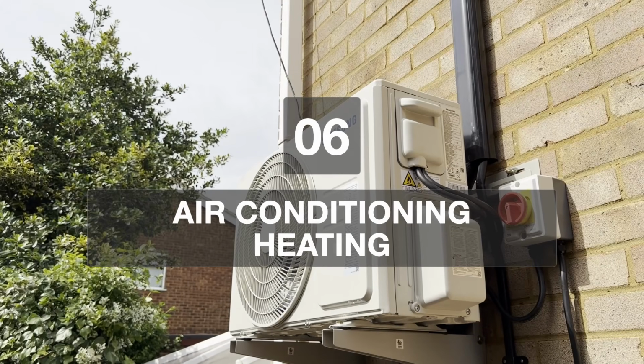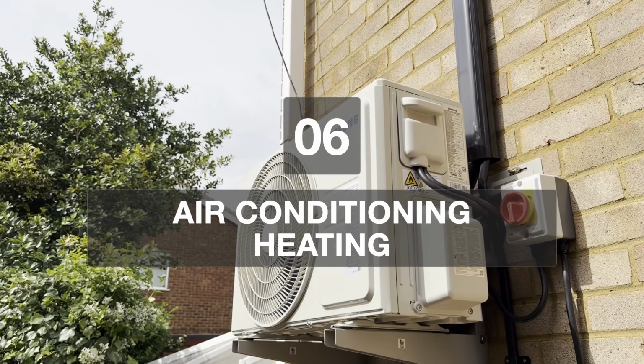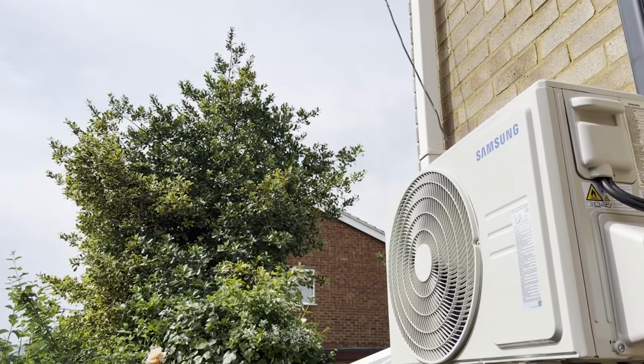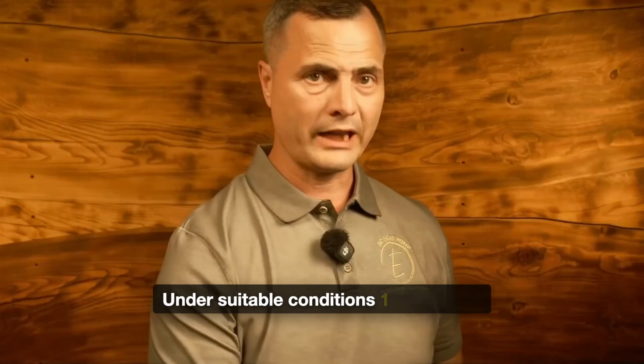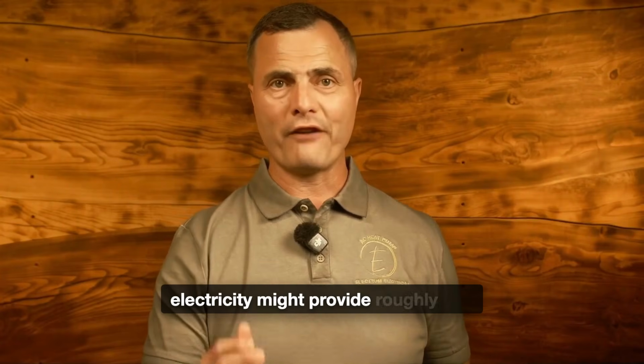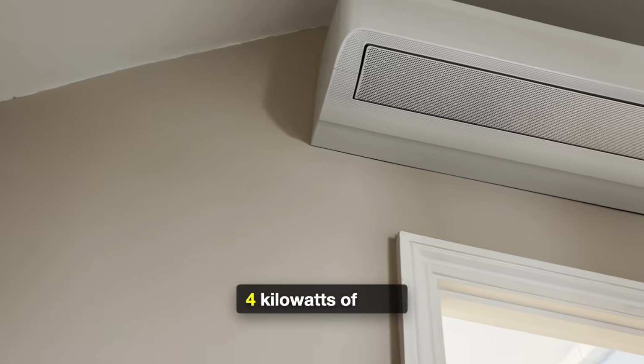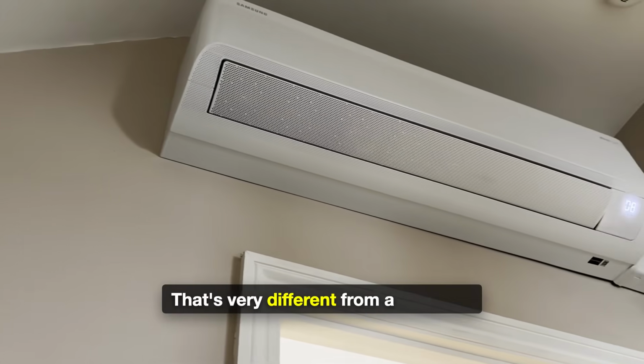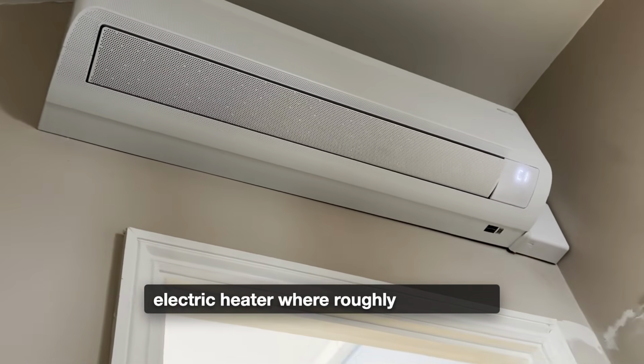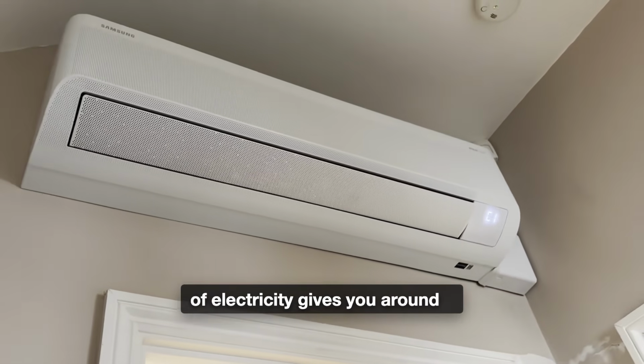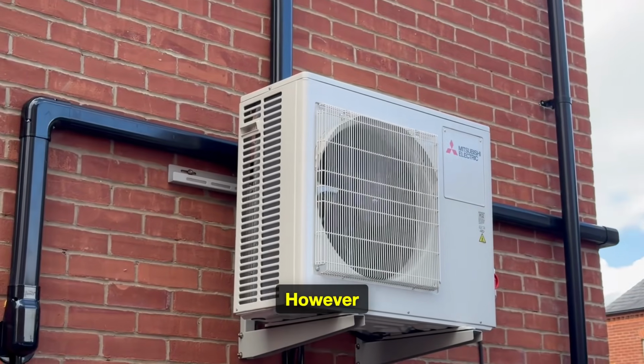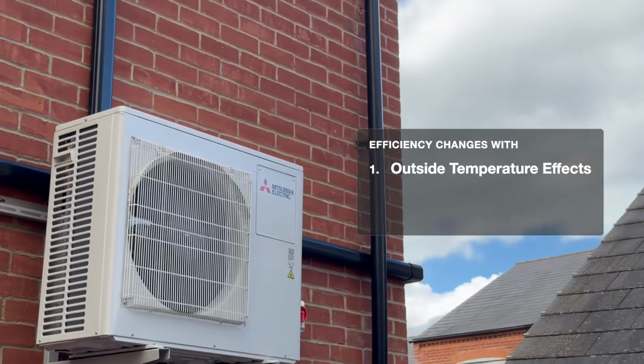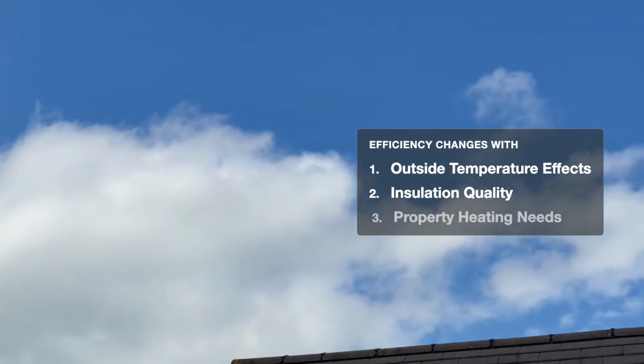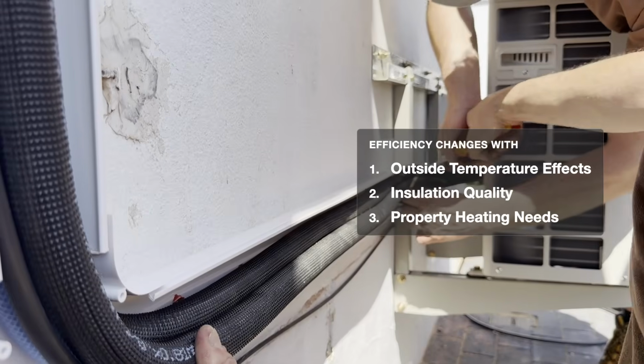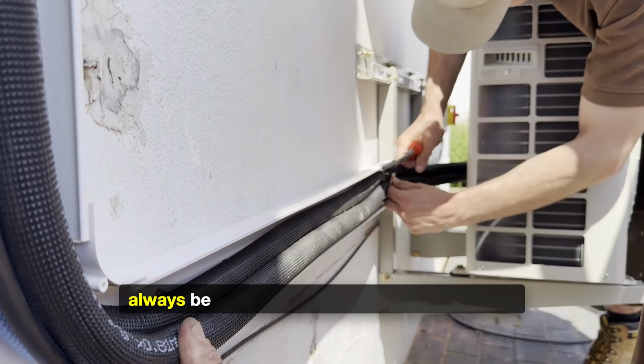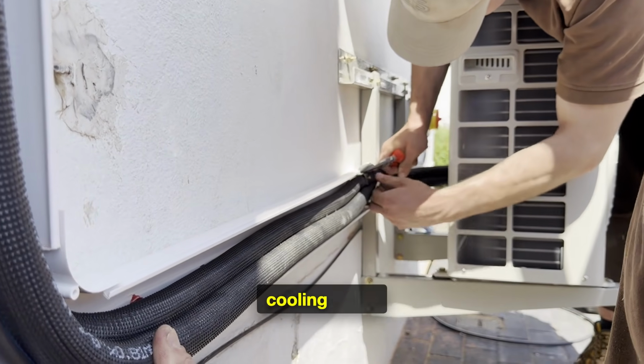Section 6. What about heating? Air conditioning can also work as an air-to-air heat pump. Under suitable conditions, 1 kilowatt of electricity might provide roughly 3 to 4 kilowatts of heat. That's very different from a standard electric heater, where roughly 2 kilowatts of electricity gives you around 2 kilowatts of heat. However, efficiency changes with outside temperature, insulation, and how much heating the property requires. So heating costs should always be considered separately from summer cooling costs.